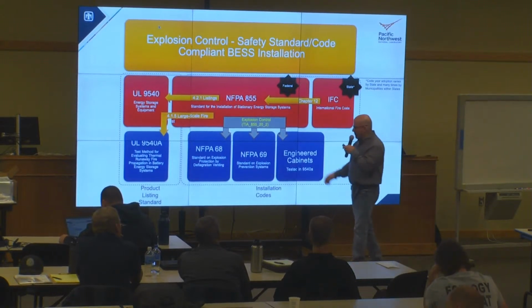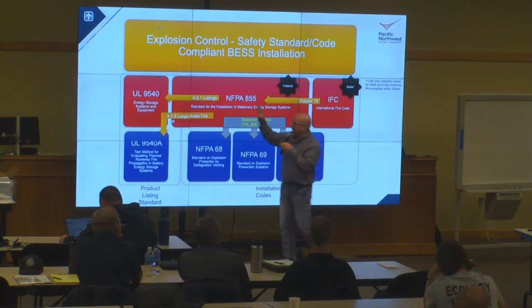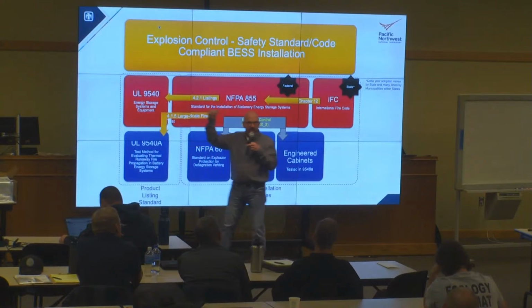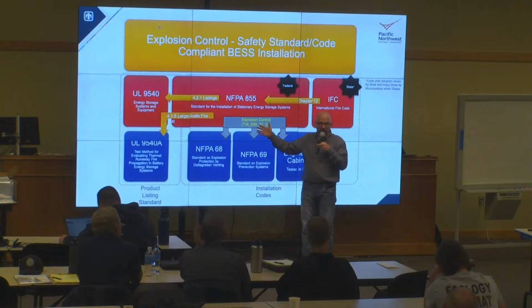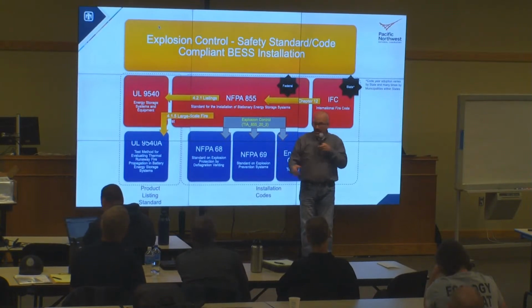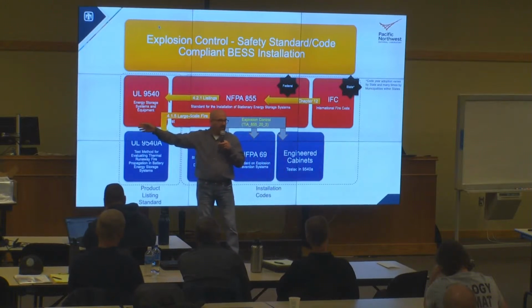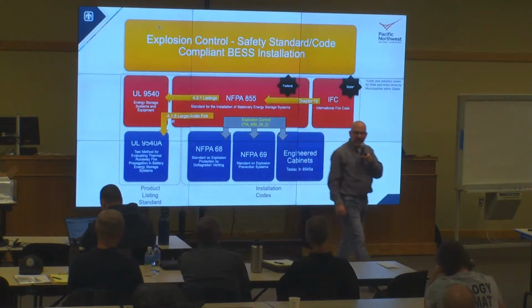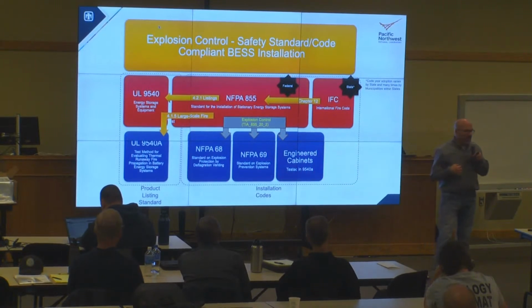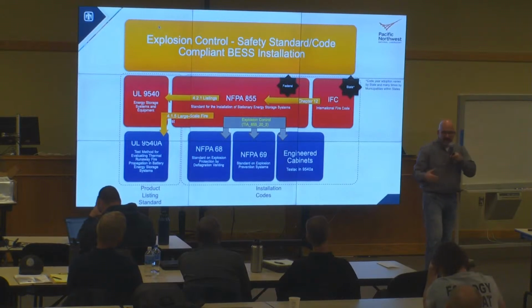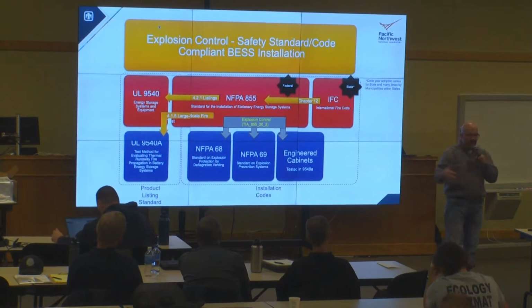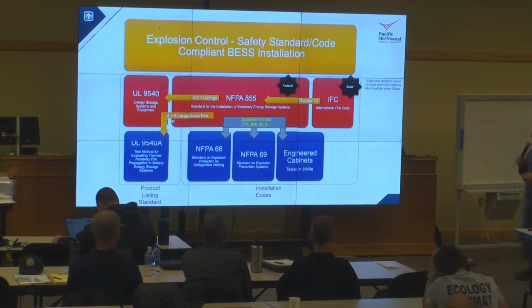The problem with this is a manufacturer could get it listed to 9540, but now the fire code or NFPA 855 says you need explosion control, and it might require a complete redesign of the system. This should be in the product listing, and it will be, hopefully next year. But I am seeing a lot of projects where, like a utility, for example, will put out an RFP for someone to bid on. They'll bid it, they're going to put in this kind of system, and they get it listed, and then the fire marshal gets involved and says, where's your explosion control? And the system's already built and already tested. And it can take months and hundreds of thousands of dollars to redesign that. So it's a big gap.